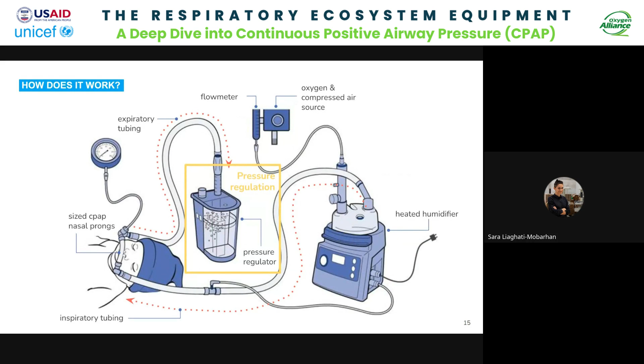Perfect. So this is typically a bubble generator with a tube that goes into the water. And what happens is the depth of the tube's end under the water surface determines the amount of back pressure that's keeping the infant's airways open. So the continuous flow of the gas that started at the blender, went through the humidifier, went past the patient, is now in the pressure regulator bottle. And this continuous flow helps to maintain a stable pressure in the delivery system. So even though the patient is exhaling, their airways still stay open.